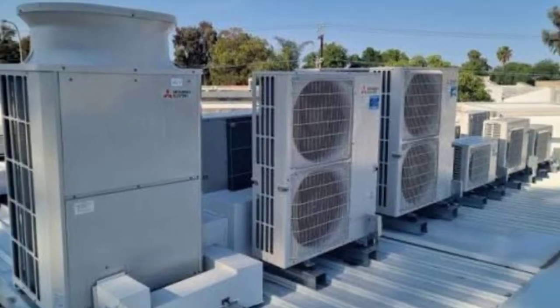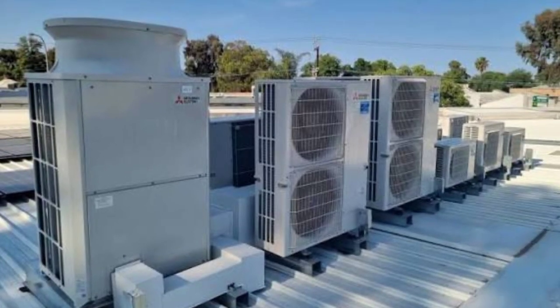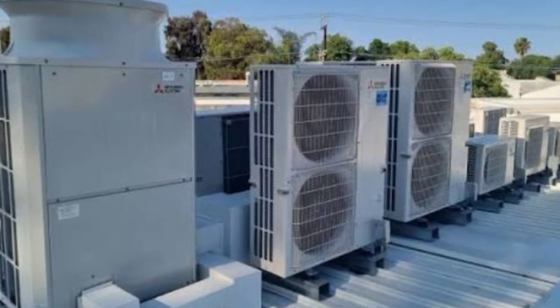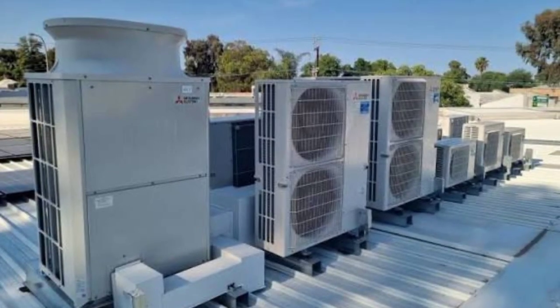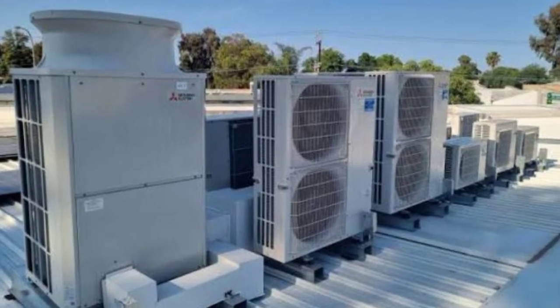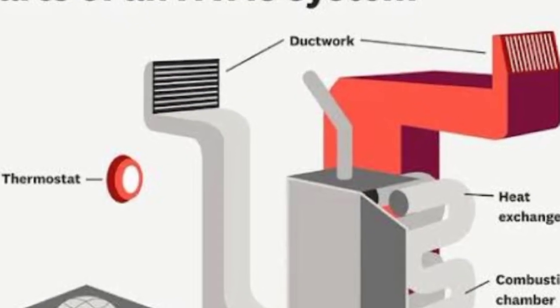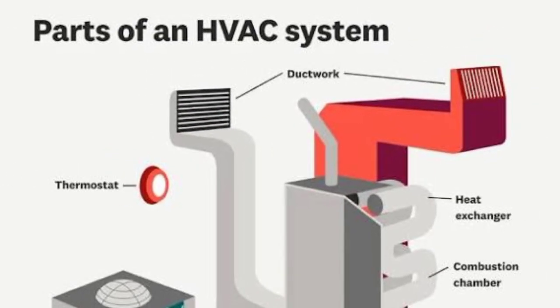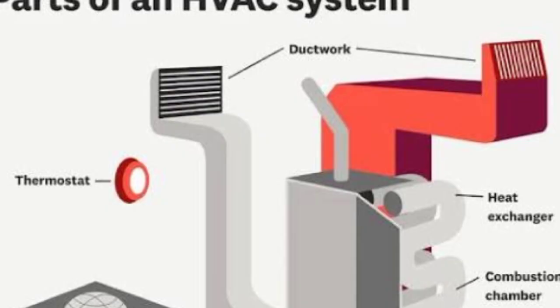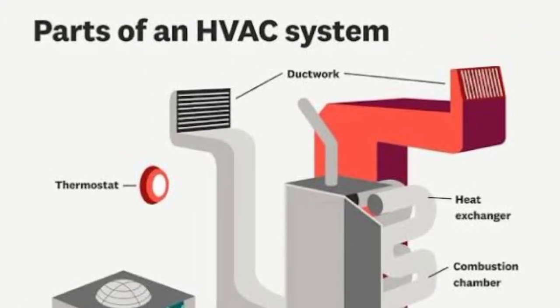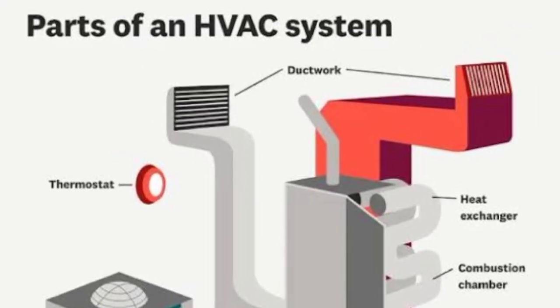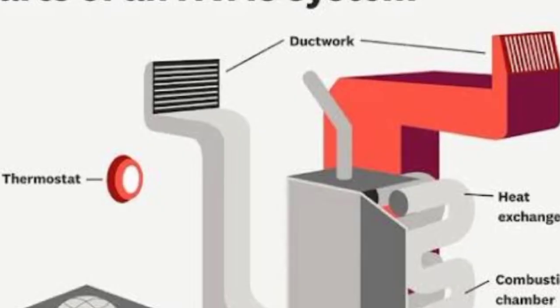When an air conditioner is too big for the space, it cools too fast. It runs for a few minutes, hits the thermostat setting, and shuts off. Then it turns back on, then off again. This is called short cycling, and it's murder on the equipment. Compressors are designed for long, steady runs. They're at their most vulnerable during startup, when refrigerant pressures are equalizing and the motor is pulling maximum current.